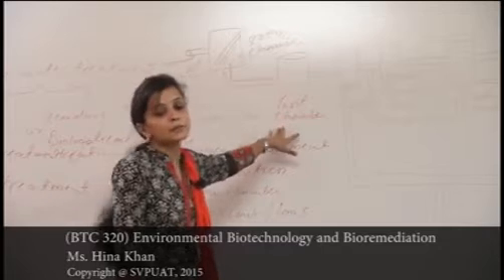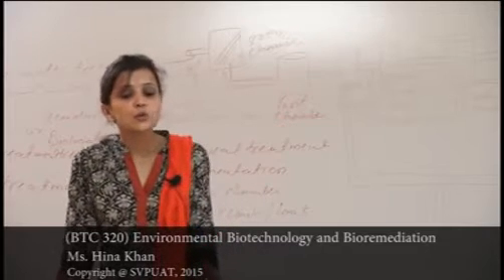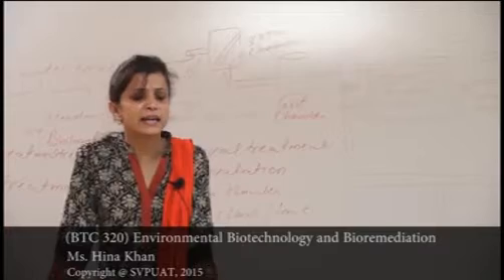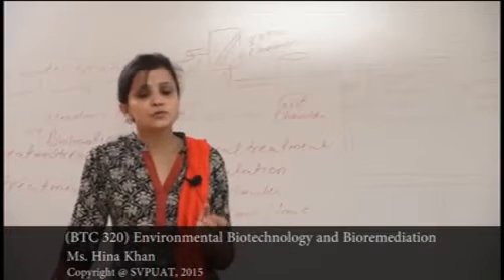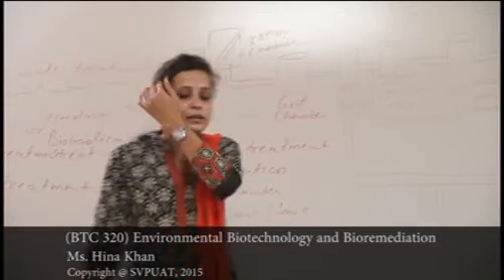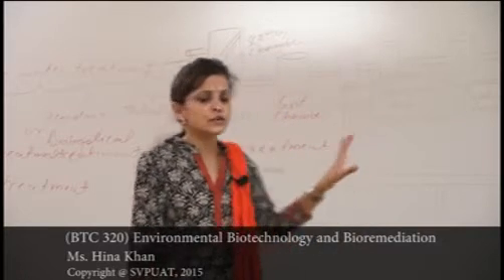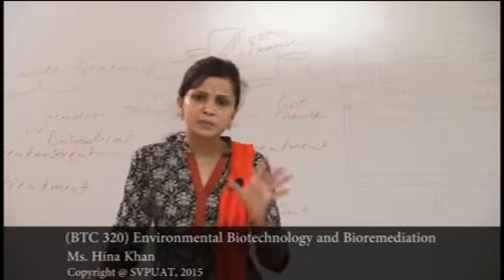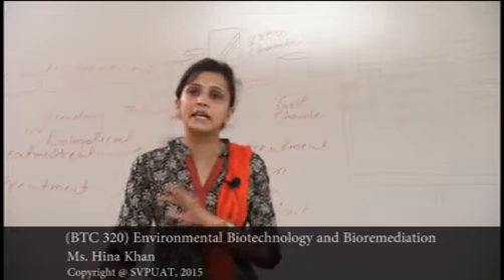Next is the grit chamber, which is present next to the screening chamber. Grit includes sand, ash, eggshells, etc., having a diameter of around 0.2 millimeters. The effluent moves to the grit chamber, where the velocity is reduced so that these particles settle down. Grit chambers can be of three types: horizontal, aerated, or vertical grit chambers.